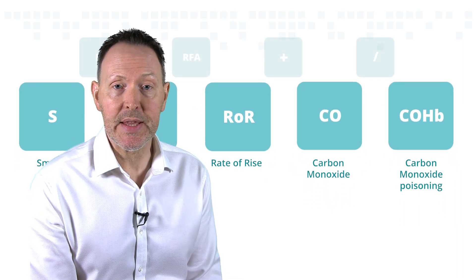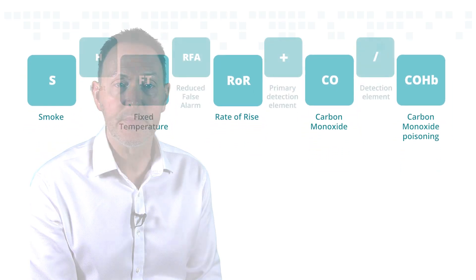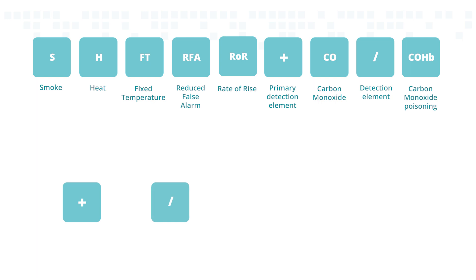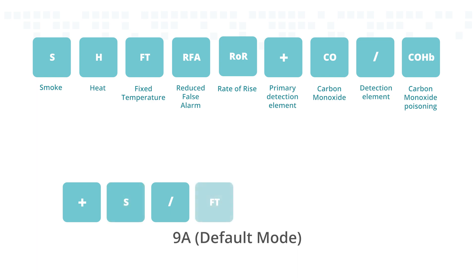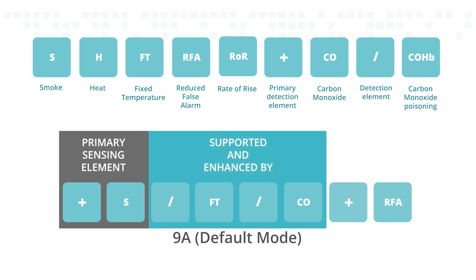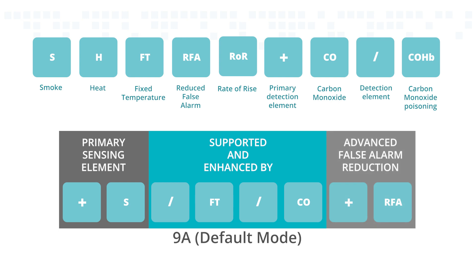As well as those letters representing the various sensing elements, there are a couple of symbols. The plus symbol denotes the primary detection element making the fire decision. The forward slash symbol denotes a detection element working to enhance the primary element. For example, in the default mode 9A, the mode string is +S/FT/CO+RFA, which shows the smoke chamber is the primary sensing element, supported and enhanced by both the heat sensor set at fixed temperature and the CO sensing element. The +RFA shows that the ACD's advanced false alarm reduction SMART algorithm is also in play. Importantly, a supporting sensing element cannot generate an alarm by itself — it's just there to confirm the fire decision reported by the primary element.